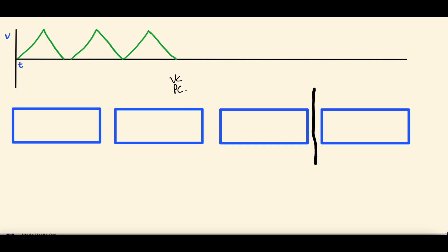In these two different modes of ventilation, the difference is what you set. In volume control, you set a tidal volume. In pressure control, you set an inspiratory pressure. The thing you're not setting in that mode is the uncontrolled variable. In volume control, you're controlling the tidal volume — the cc's of air the ventilator pushes into the lungs with each breath. But the uncontrolled variable that results is the pressure — the inspiratory peak pressure. In pressure control, you set the pressure, and the uncontrolled variable is the tidal volume.